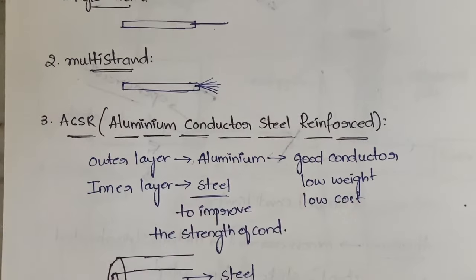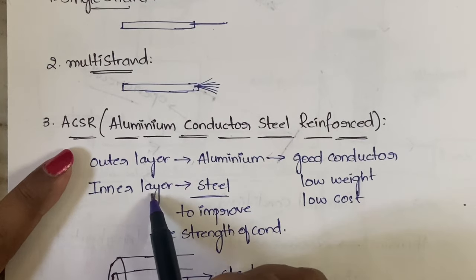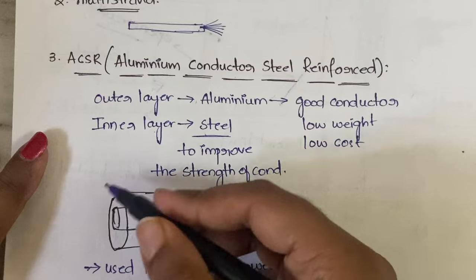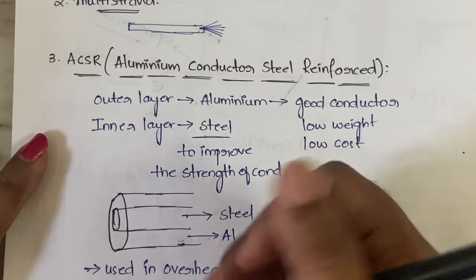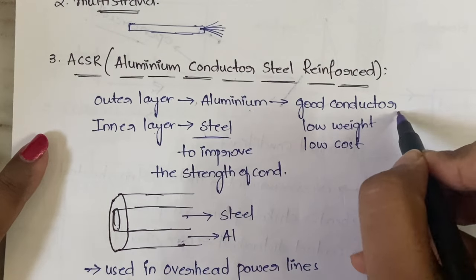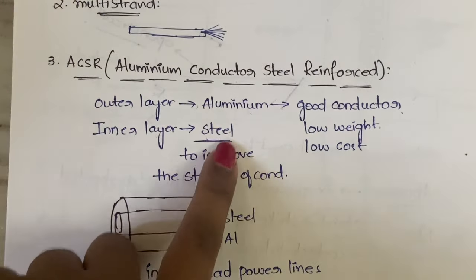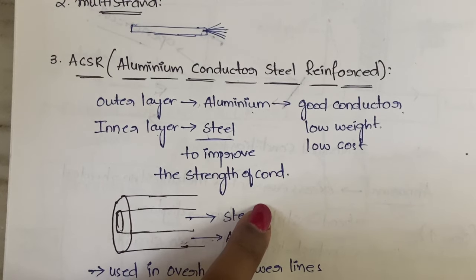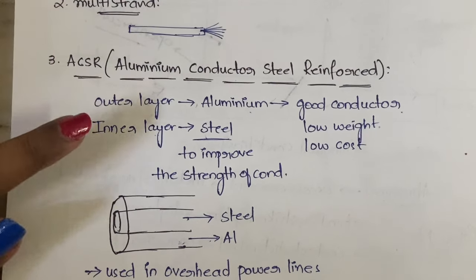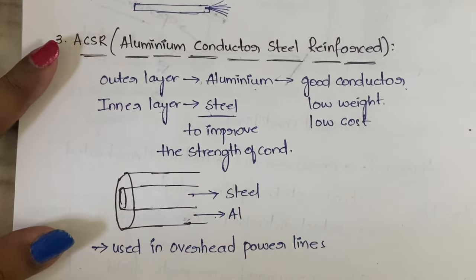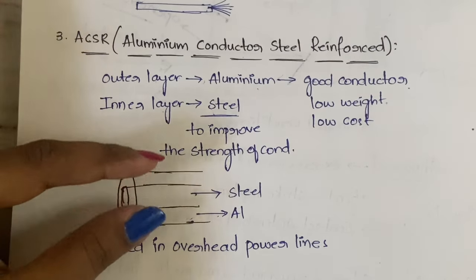Next is ACSR — Aluminum Conductor Steel Reinforced. In ACSR, the outer layer is aluminum and the inner layer is steel. Aluminum is used in the outer layer because it is a good conductor with low weight and low cost. Steel is used in the inner layer to improve the strength of the conductor. ACSR is mainly used in overhead power lines.